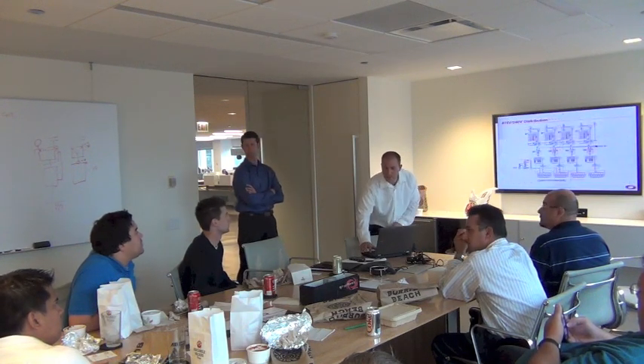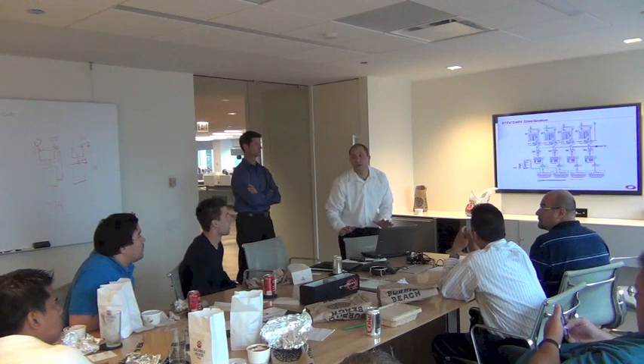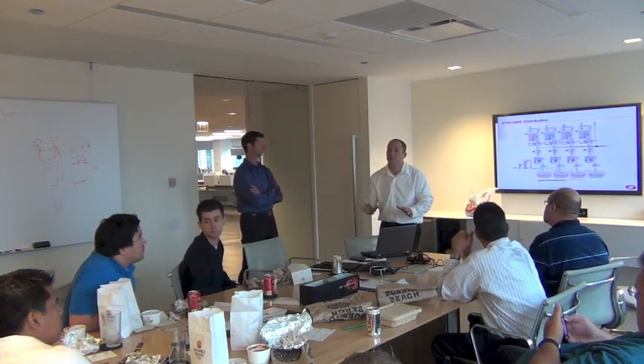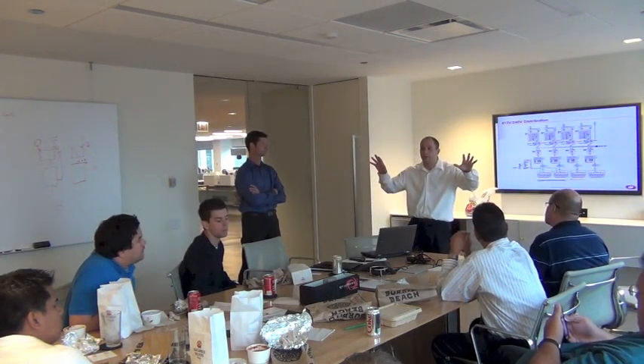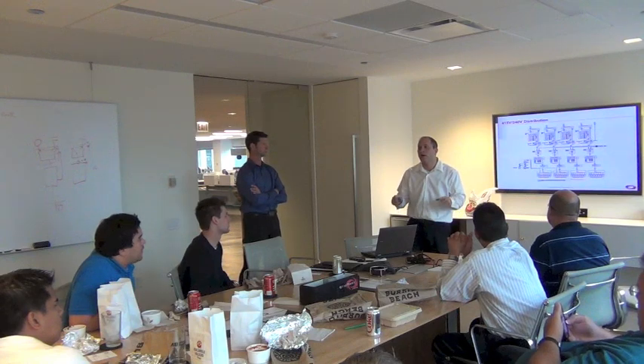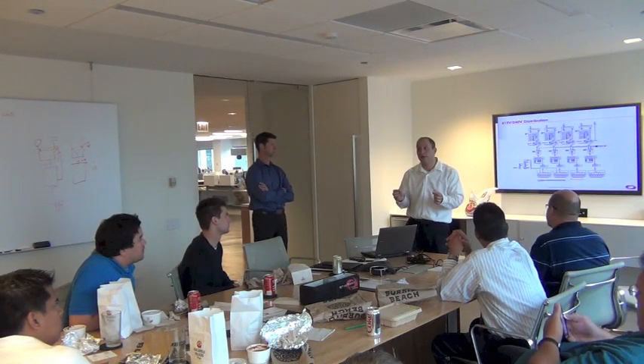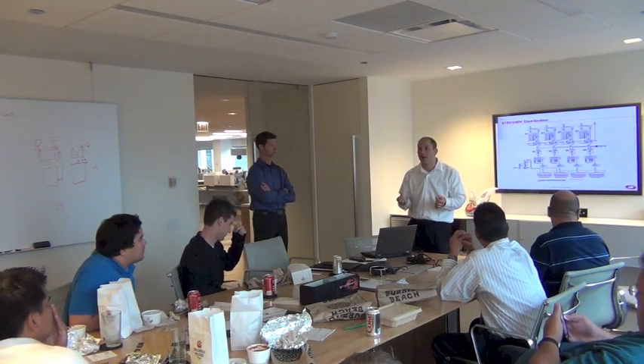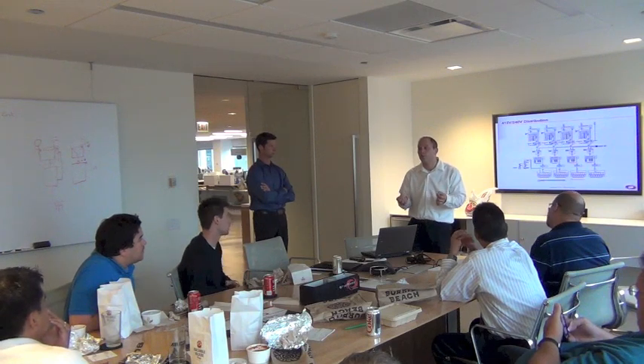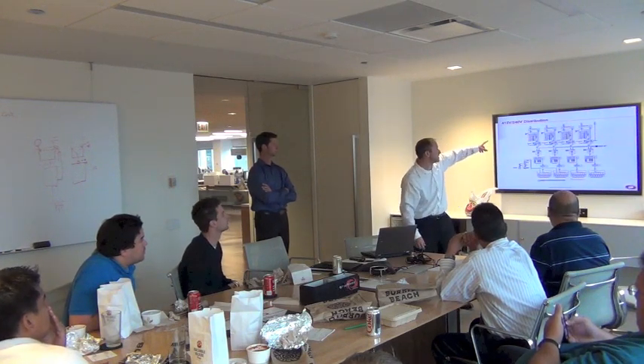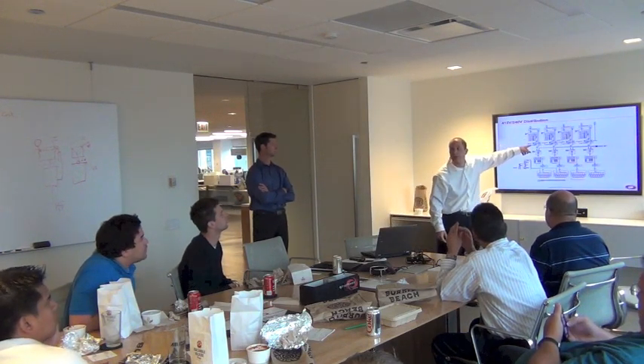Is there some medium voltage? No, we don't have any medium voltage UPSs, but we do have medium voltage installations where we're generating at medium voltage. But at some place we've got to step it down. And if we're going to parallel massively at medium voltage, we need to understand what that ride through time is. It's not to say we can't do it, but it's more challenging.